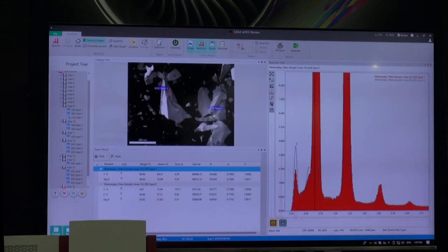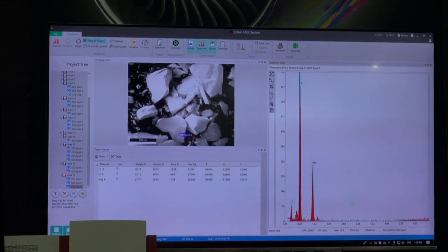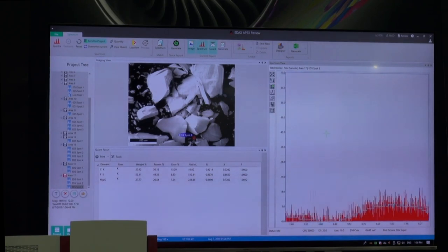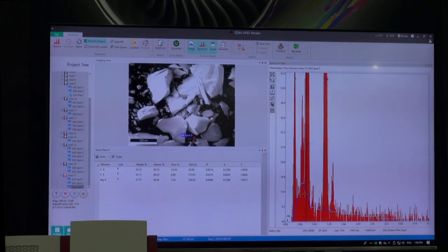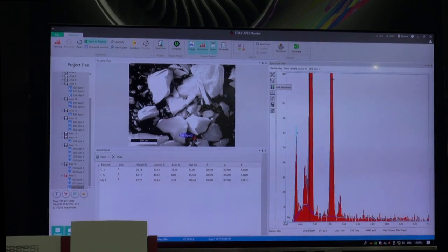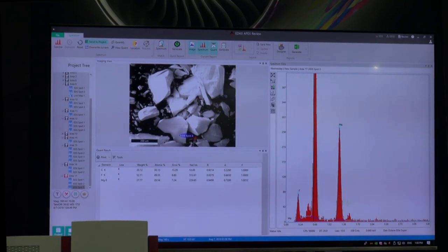If I'm trying to do qualitative analysis — is there magnesium there, get an idea of how much — the SNIP model is much, much better. The SNIP model is just a math filter: it gives you the peak, it gives you the drop, and it gives you a pretty curve in the low energy range. Whether it's physically correct is another question, but you don't get the negative count situation where the background goes above the peak. So it's much easier to pull apart close peaks or overlaps — whether it's magnesium fluoride or something else.